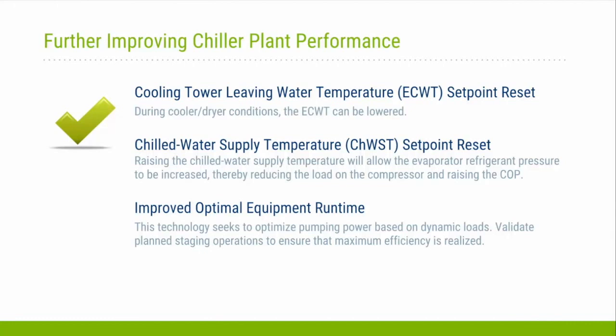Chilled water set points: the vendor does adjust the set point, but in their literature they emphasize optimizing the flow rates through the chiller evaporator and the condenser, and trying to synchronize that so that there are no low delta T issues, which they were able to do successfully. You're getting the proper flow rates through the chiller and then out to the building on your secondary loops. By doing that, they would actually recommend possibly running lower chilled water temperatures, which in a lot of parts of the country are necessary for humidification or dehumidification control, and yet do that in a way that it not only allows you to dehumidify, but even run your VAV systems in such a manner that you're not paying a penalty with potentially higher static pressures, or not able to maintain static pressure, I should say, due to VAV boxes not being satisfied.